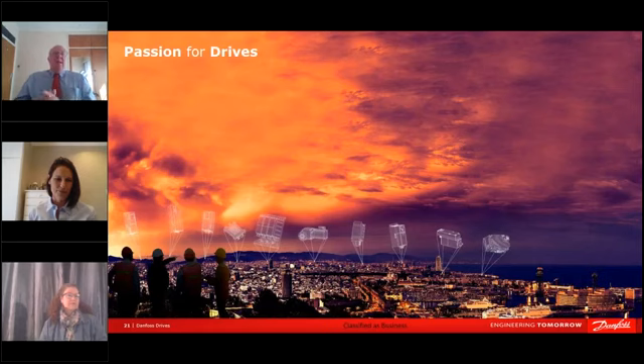Now, we have an area where we conducted this. It's not actually on a mine, but it was a water and wastewater plant in Europe. The payback period obviously depends on the size of the drive, the kilowatt rating of the drive. We looked at some 800 kilowatt drives, and on average, the payback period on a drive, especially around the 800 kilowatt size, is around an 18-month period.